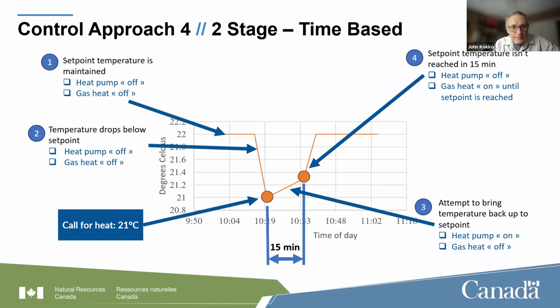And then if the heat pump in that time frame can't hit set point, so it can either come up a little bit, it can go down a little bit, it doesn't matter. It says, okay, 15 minutes later, have we hit the set point in the house? If yes, then turn the heat pump off. If no, then turn on the gas backup heating.